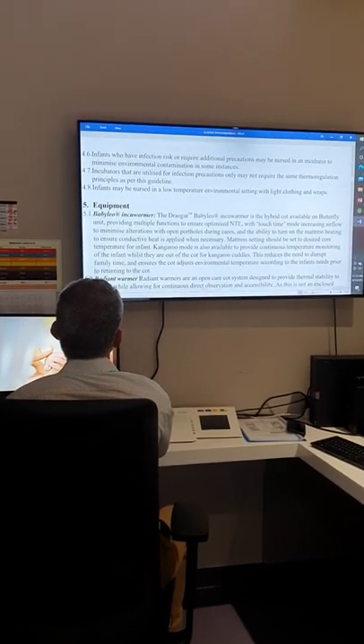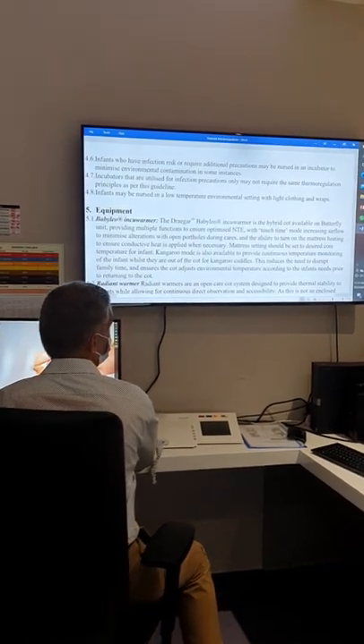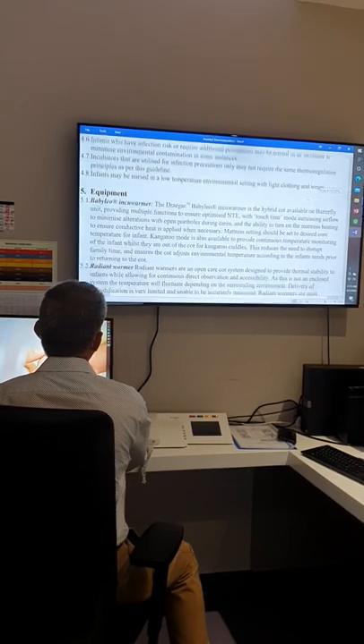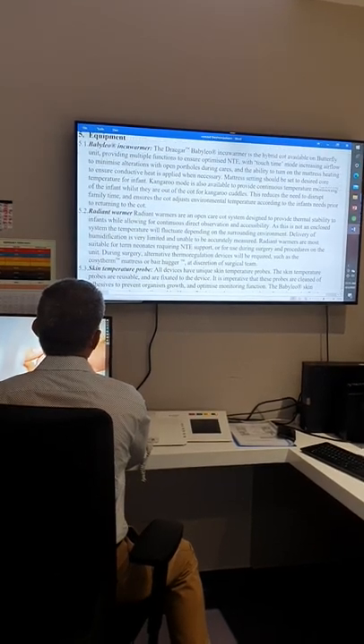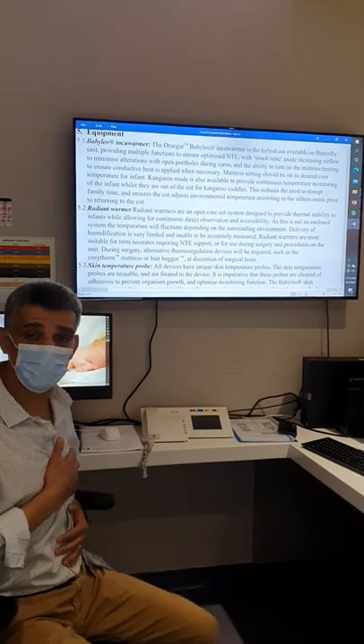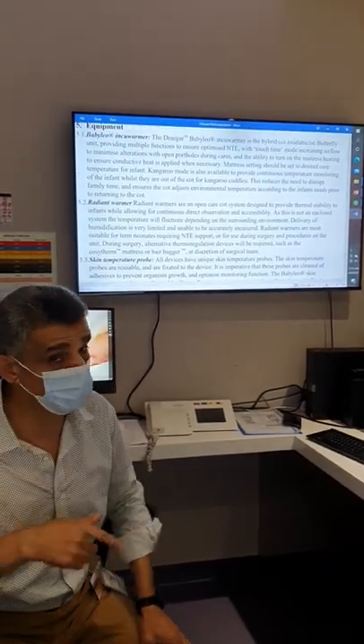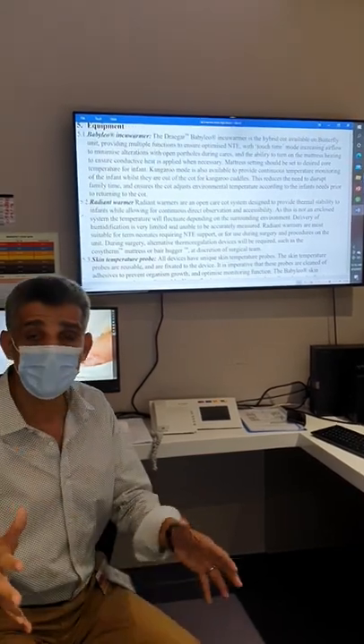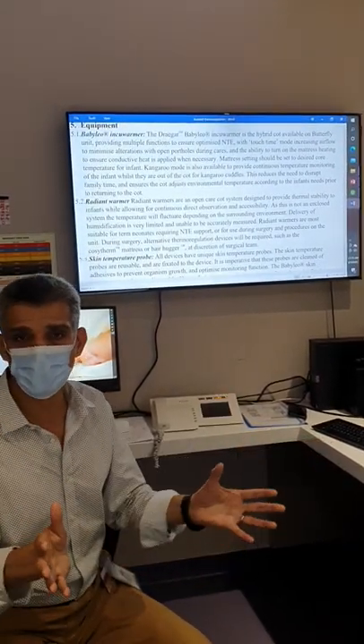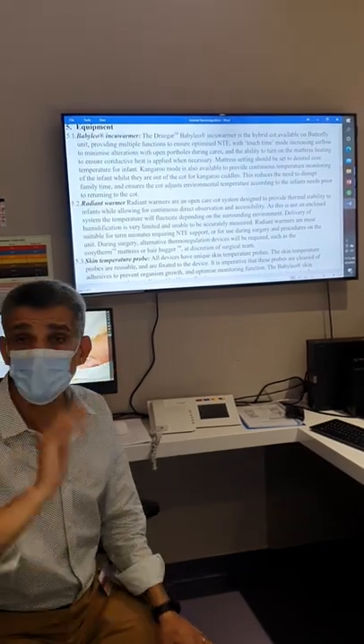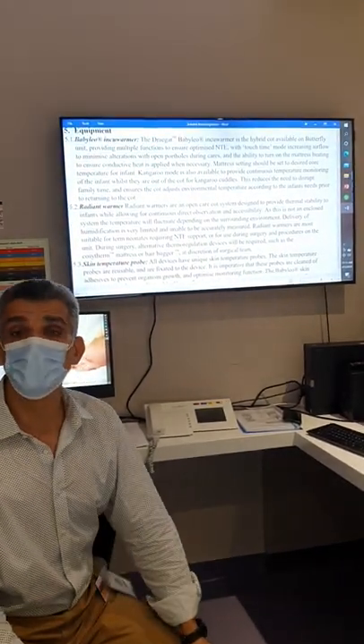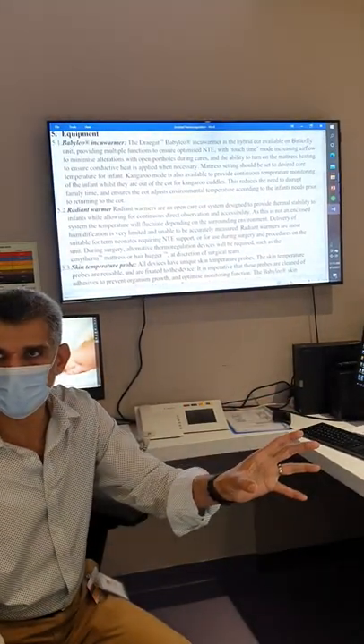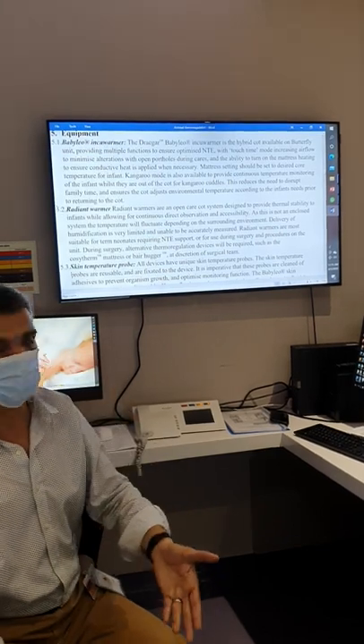Equipment: our incubator can provide assistance. The skin temperature probe is very important to monitor temperature, but that's not enough — we also need to check axillary. The skin temperature probe feeds back to the incubator to control the environment; we don't use it to assess the baby's vital sign temperature. This is only a servo control temperature, not for vital sign assessment.